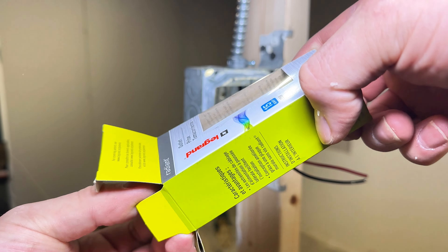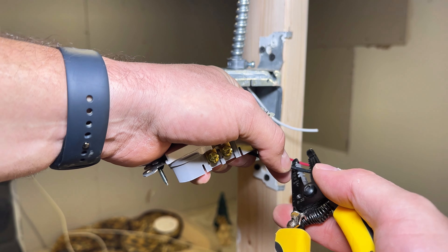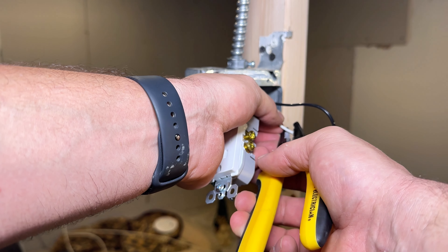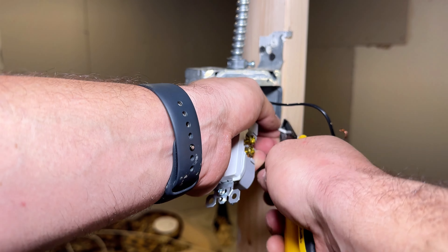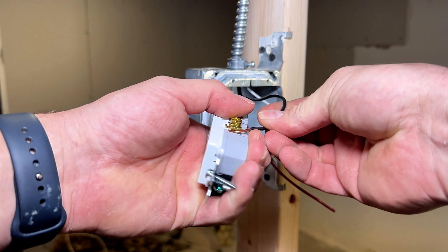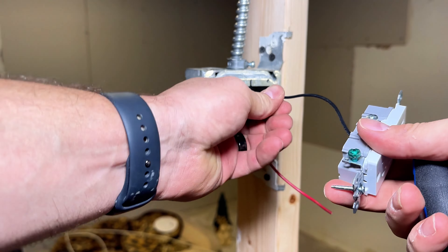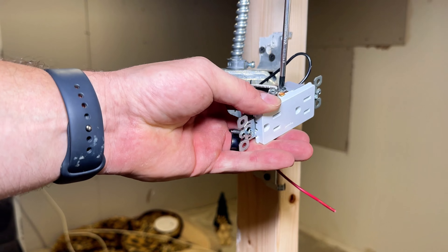Here we go — we're going to wire the outlet. You've got your power here, your hot — look at that pretty hook. Put a nice little hook on the neutral too. Make sure you put it on clockwise with these screws. Your hot is always going to go to the gold screw, and your neutral will be silver. Clockwise on the screws so it tightens in around your hook.